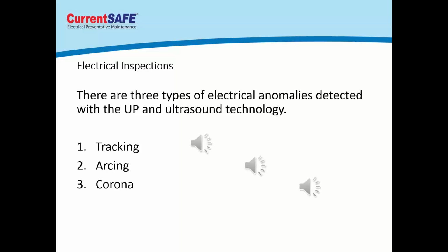So those are the three things that we can detect in the electrical world. It's really good as well for doing bearing inspections, air inspections, and inspections on vacuum systems, those kinds of things as well. So there's a mechanical side to it that you could benefit customers with as well. I know when I spent a lot of years in the field, that was one of the things our customers liked to do when they found out we had this, is come and do air inspections. Especially with steam traps as well, so we could listen and make sure steam traps were working in their facility. We could hear and make sure that they didn't have any bearings going out. We could hear air leaks. The more air leaks we repaired, the more efficient their air system became, the less that they had to pay in energy to keep compressed air in their system. So it's a great benefit and other means and methods as well, other than just electrical distribution inside your customers' facilities.